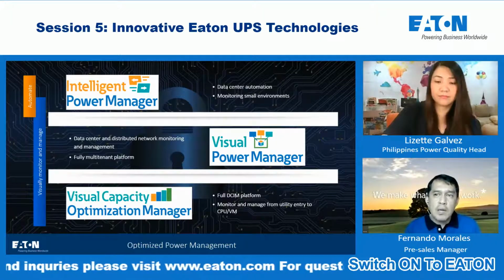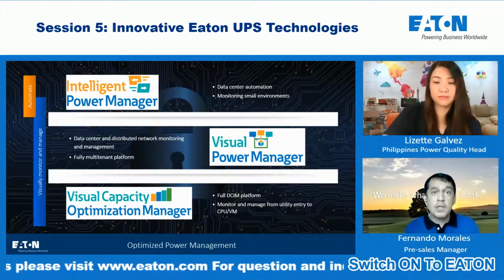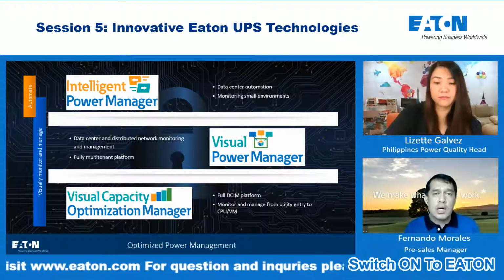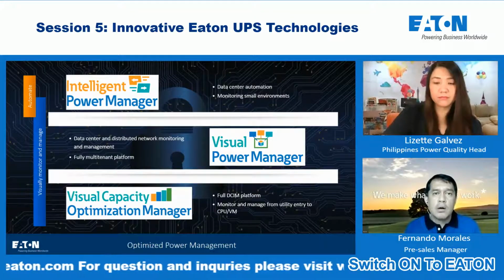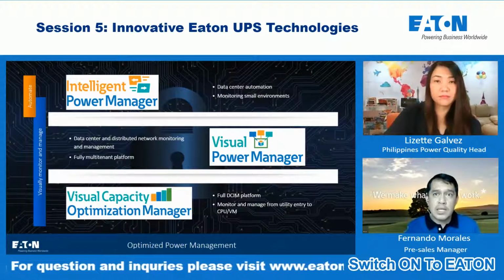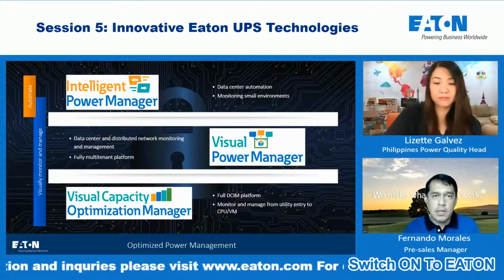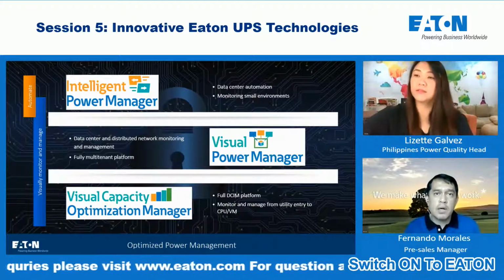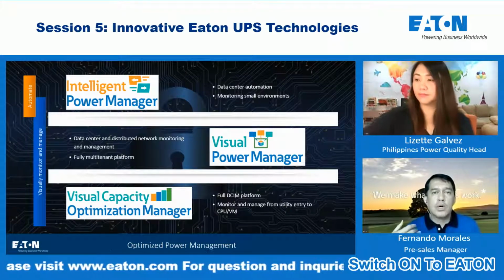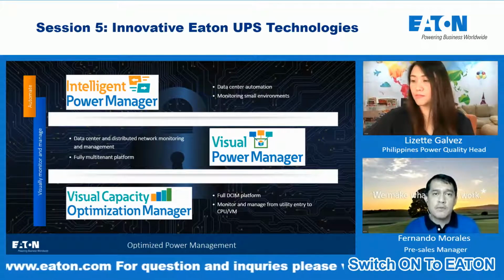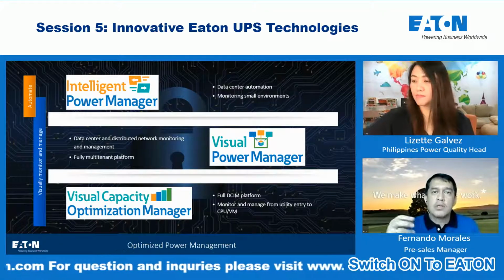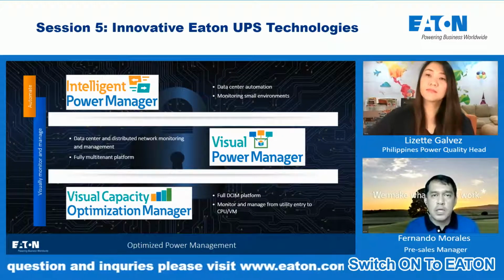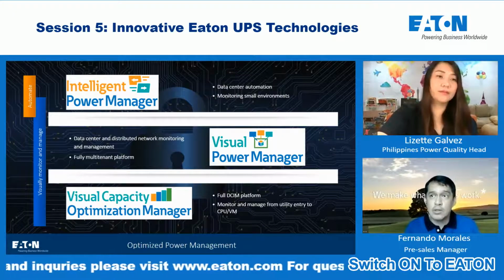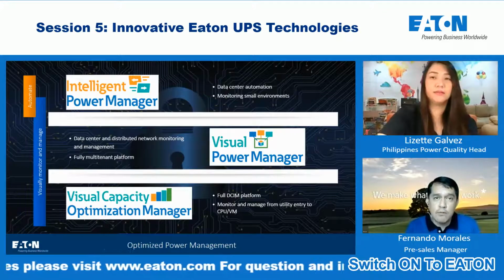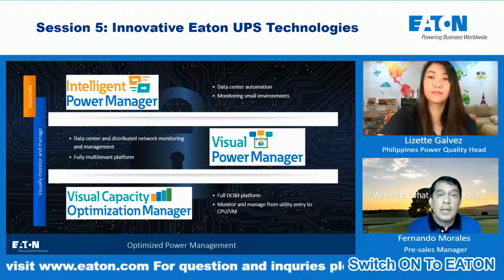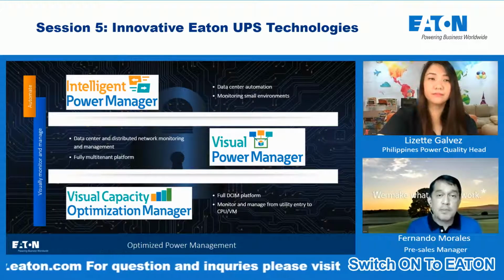And if worst comes to worst and the generator really has a problem, with IPM we can program it so that, for example, after 15 minutes of continuous battery usage, we can gracefully shut down critical servers, or if they have a mirror site, we can initiate a transfer from the main site to the mirror data center site, especially in a virtualized environment. That's the purpose of IPM — it's not only for monitoring, but it helps customers attain the uptime that they require.